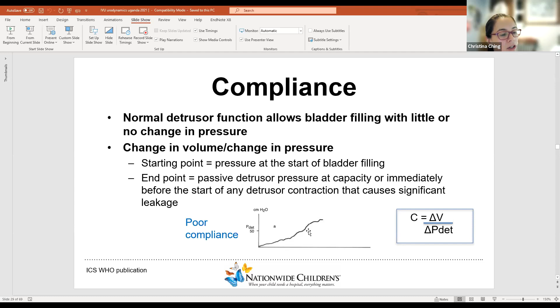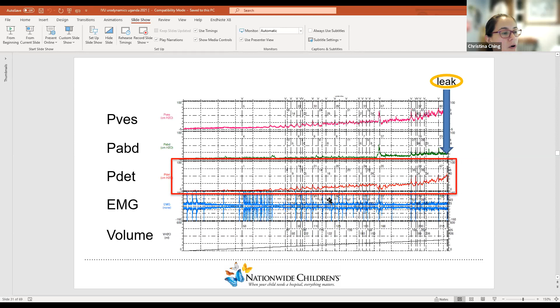This is normal. Here we see that over time, the pressure starts to rise until the patient has a leak. This shows that there is a change in compliance. This is not a compliant system because it is not holding volume at a low pressure. The pressure is actually rising.